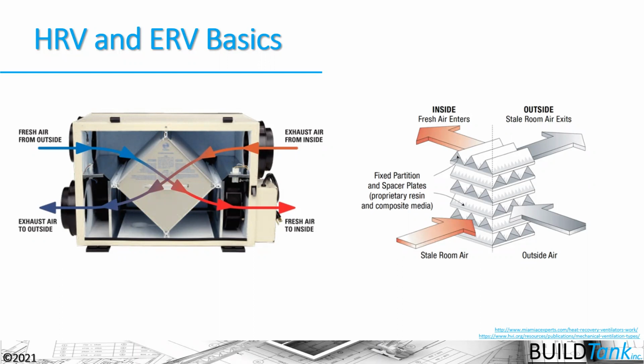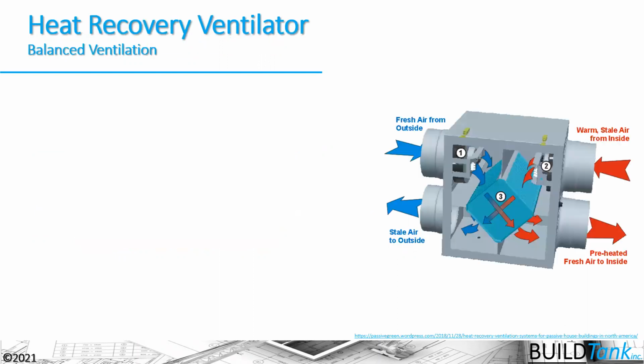So you can think of it as a heat exchanger, but a heat exchanger that also has the ability to transfer moisture in specific cases here. Because what we know is that moisture, heat, and energy always move from higher concentrations to lower concentrations. So they're always going to move across these core heat exchangers or moisture exchangers without mixing the air, if we can run them correctly.